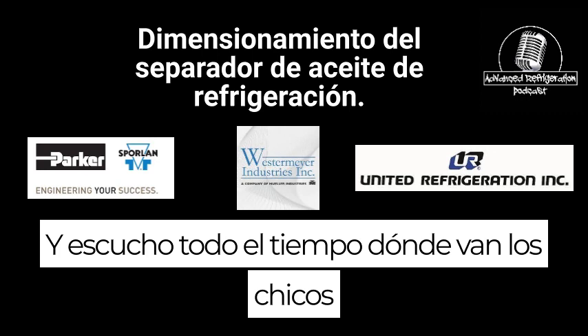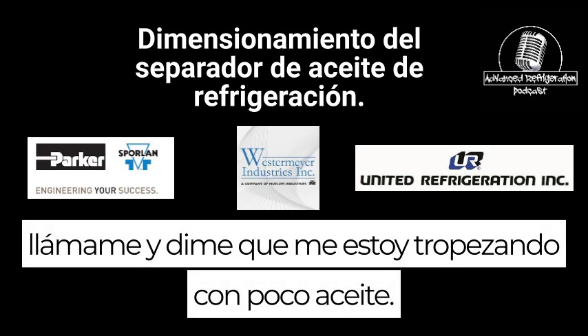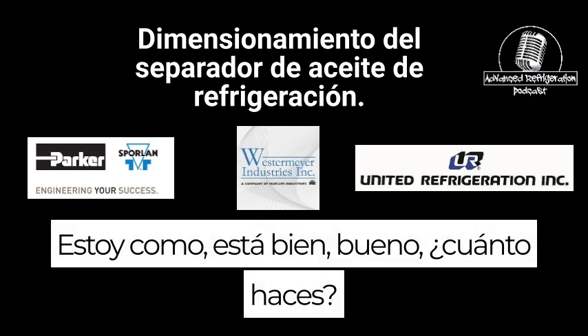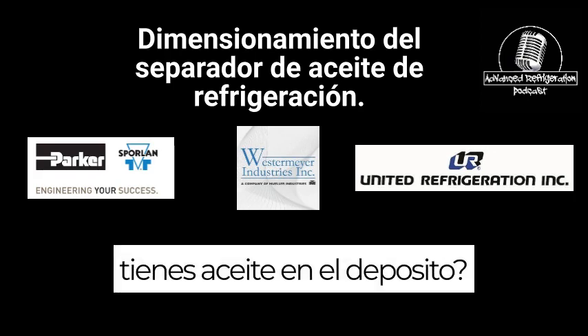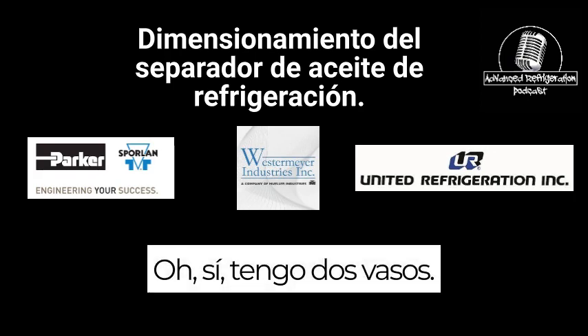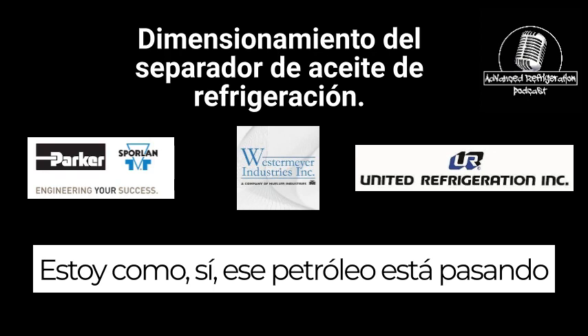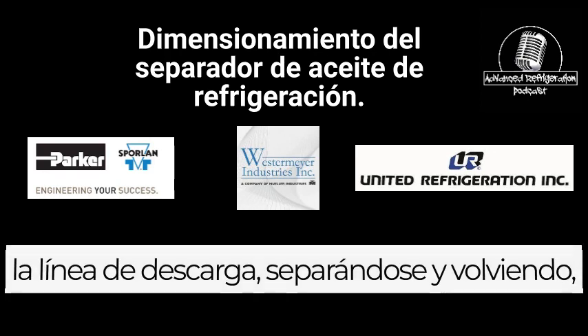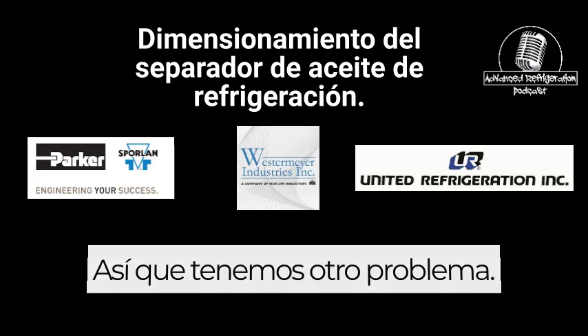And I hear all the time where guys will call me and say, I'm tripping on low oil. I'm like, all right, well, do you have any oil in the reservoir? Well, yeah, I've got 2 glasses. I'm like, yeah, we're not there. That oil is going through the discharge line, getting separated and going back, and it's getting stored in the reservoir. So we've got another problem.